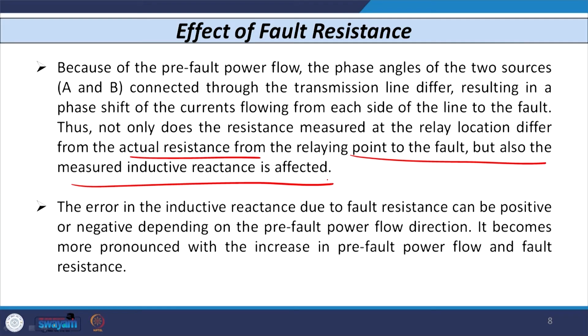So, the error in the inductive reactance part due to the fault resistance, whether in the real part or the imaginary part, can be positive or negative. That depends on in which direction power flows before the fault, from A to B or from B to A. This is very important. If the pre-fault power flow is from bus A to bus B, then the measured reactance at the relay location is less than the inductive reactance from the relaying point to the fault point. So, the relay may maloperate even though the fault is beyond the zone of the relay, that is, an external fault. That is nothing but overreaching of the relay, because of the reduction of this inductive reactance or imaginary part.